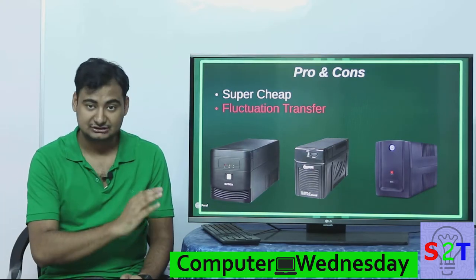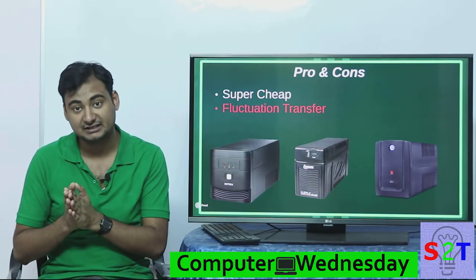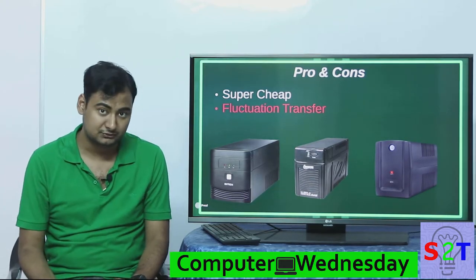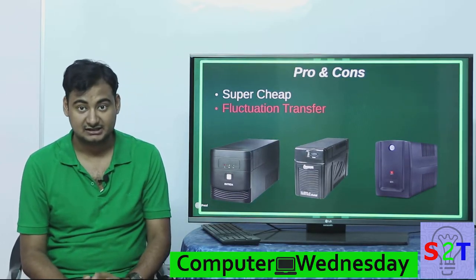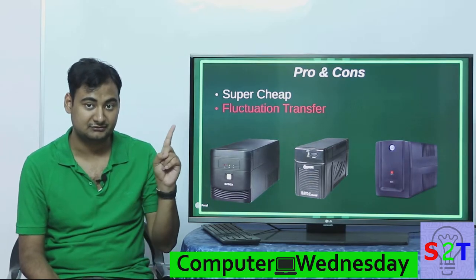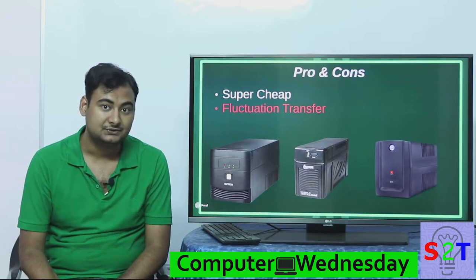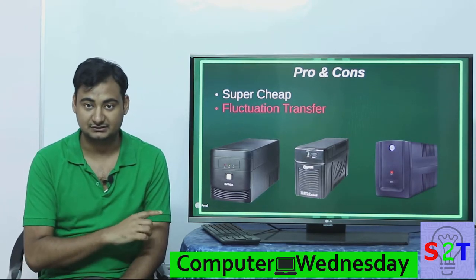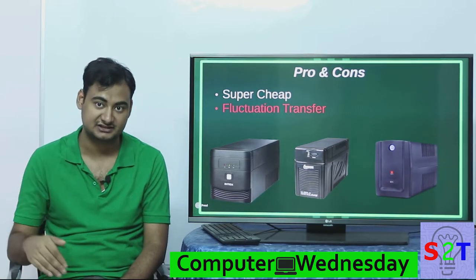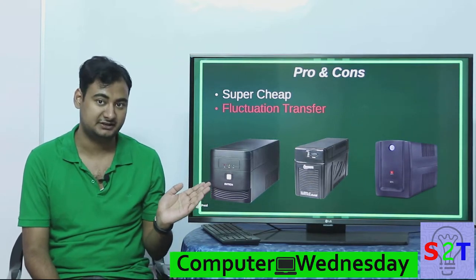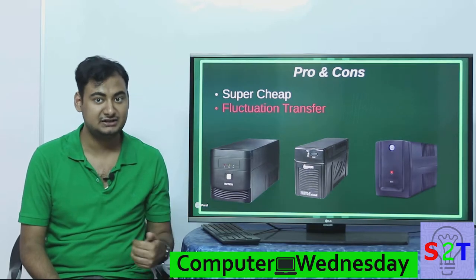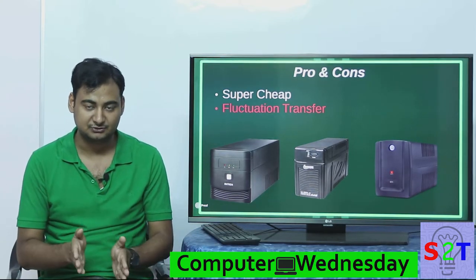Your equipment is actually experiencing a voltage fluctuation during that switching. Furthermore, if the voltage fluctuation is within the auto transformer's handling range — say plus or minus 5 volts — it won't do anything, and that fluctuation goes straight to your equipment. For this reason, if you have very sensitive electronics, you may want to use an online UPS instead. If you have constant fluctuations of 5–6 volts, your equipment can still get damaged because this type of UPS does not prevent those — it only switches to battery and back each time.